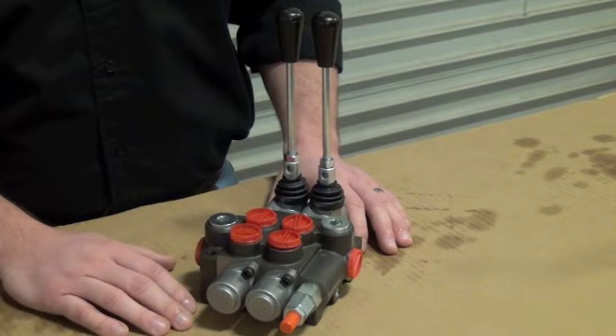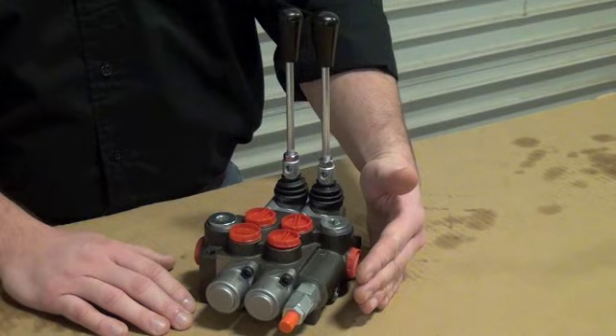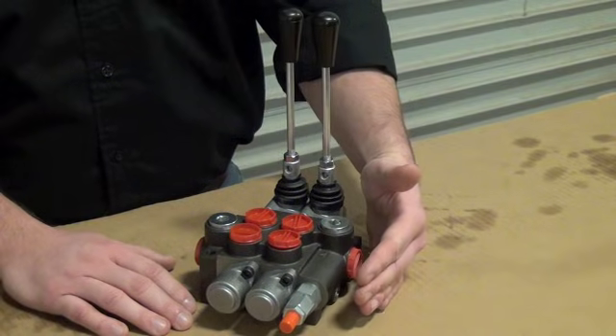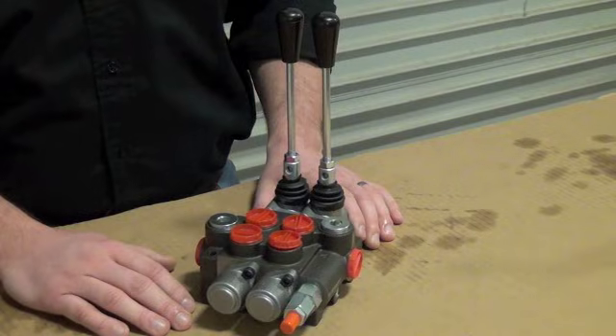Conversely, a closed center valve blocks the flow of oil from the pump and does not allow it to pass to the tank while the valve is not in use. A closed center type valve is mostly used with pressure compensated pumps.